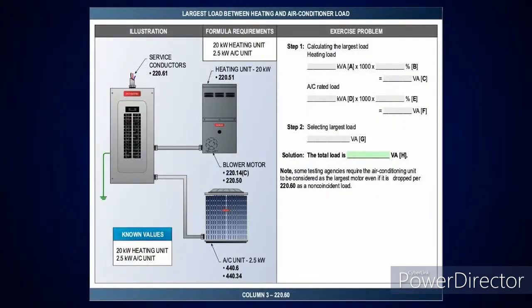Now you look here. You got a 20 kW heating unit and a 2.5 kW AC unit. Pretty easy to say here which non-coincident load's the largest, and that's going to be your heating load.